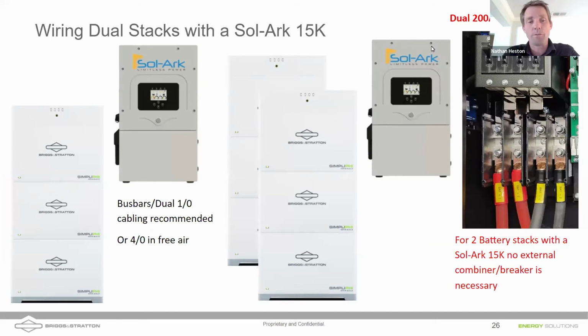And one of the nice things about the 15K is you have dual battery inputs. Those dual battery inputs allow you to make 2 battery connections. That means you can use the 15K essentially as your combiner if you're doing 2 stacks. And if you're doing a single stack, we actually recommend using dual 1/0 cabling from that single stack. So double lug at the battery and come out through 2 1/0 connections, one into each of those battery inputs on the 15K.